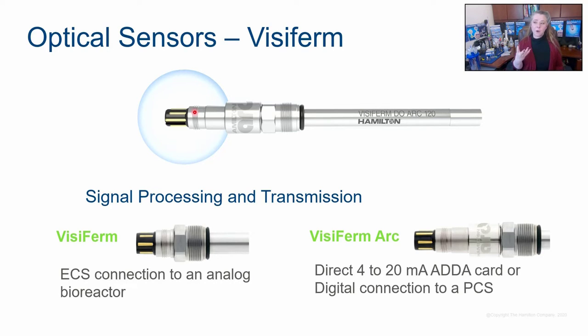Remember I talked about polarographic probes just a second ago? Hopefully you didn't forget. It was just briefly ago. Those are electrochemical probes. They have a nanoamp signal. When people wanted to start replacing polarographic with optical, they needed to have a probe that would mimic that nanoamp signal, but they wanted all the benefits and ease of use of optical. So Hamilton uses what's called the Visiferm ECS probe that mimics the exact same nanoamp signal as a polarographic probe, but it's an optical sensor.